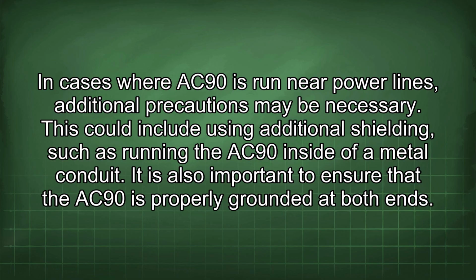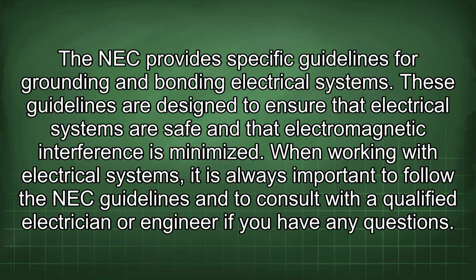In cases where AC90 is run near power lines, additional precautions may be necessary. This could include using additional shielding, such as running the AC90 inside of a metal conduit. It is also important to ensure that the AC90 is properly grounded at both ends. The NEC provides specific guidelines for grounding and bonding electrical systems. These guidelines are designed to ensure that electrical systems are safe and that electromagnetic interference is minimized.